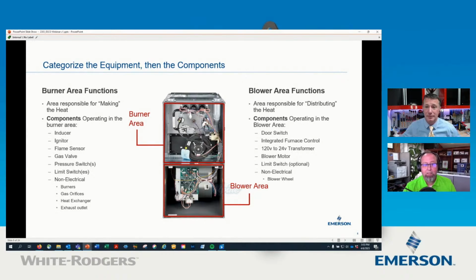Sure. And you say, well, wait a minute, Clifton, we've got three wires going to that inducer now, not two, and now I have to figure out what else is going on there. Well, the sequence of operation never changed. It still stays the same. If you are making a call for heat, the first thing that has to happen is, well, let's back up. You could have an internal thing that you can't see, and that is that the board could be checking to make sure the limit switches are all closed and that circuit is done.